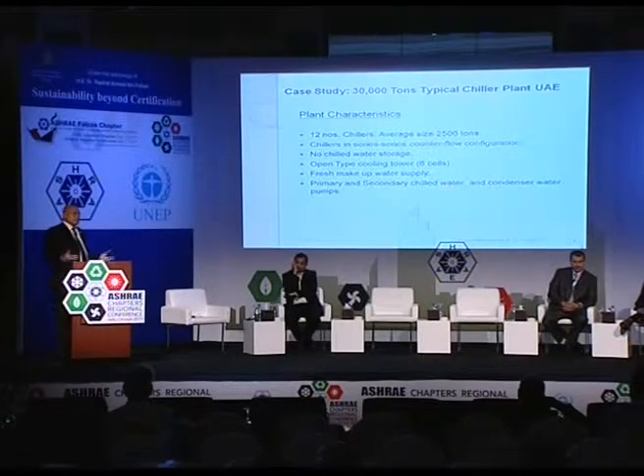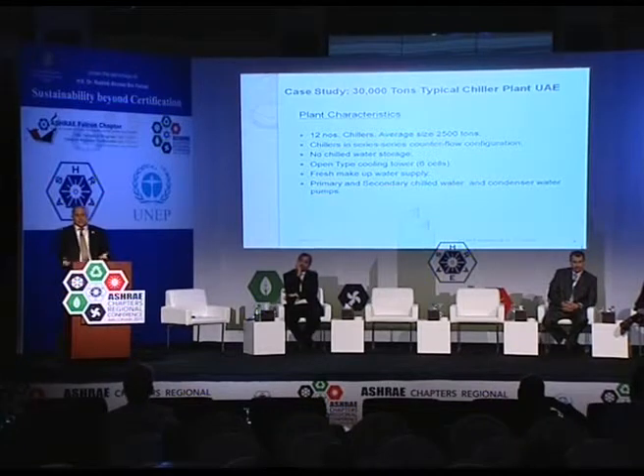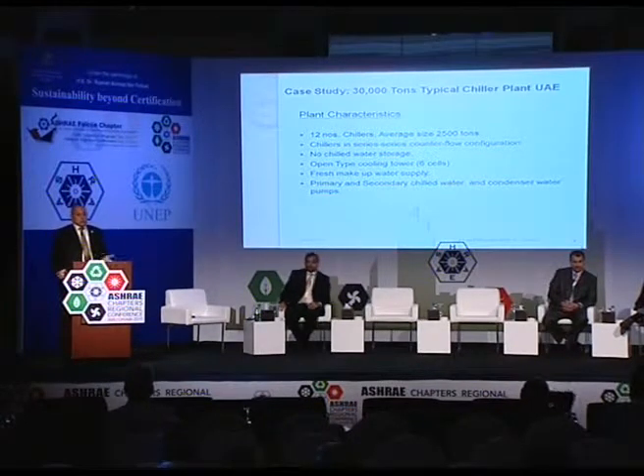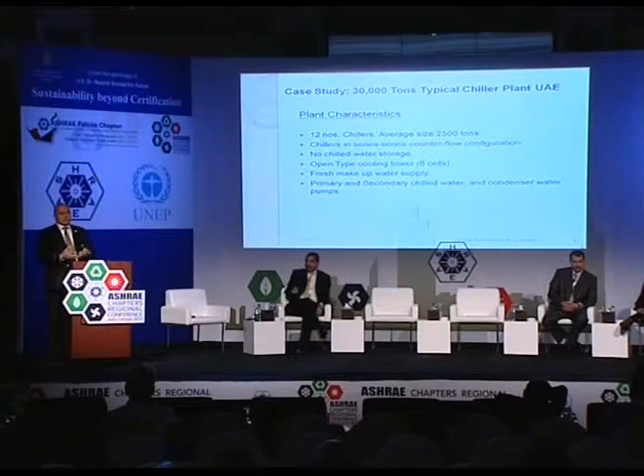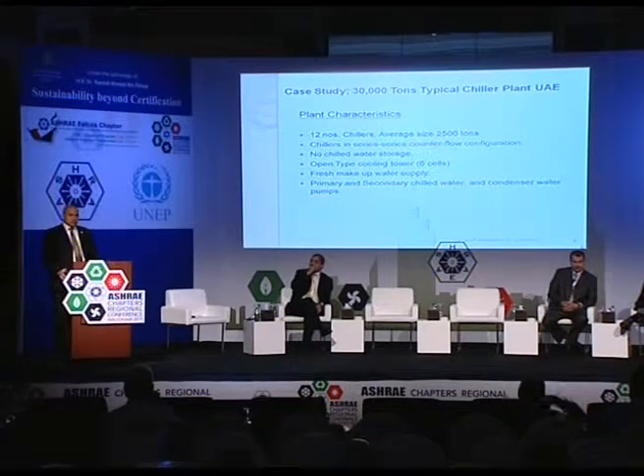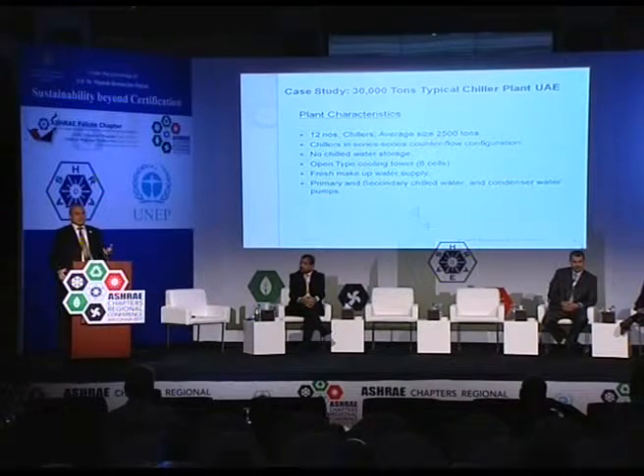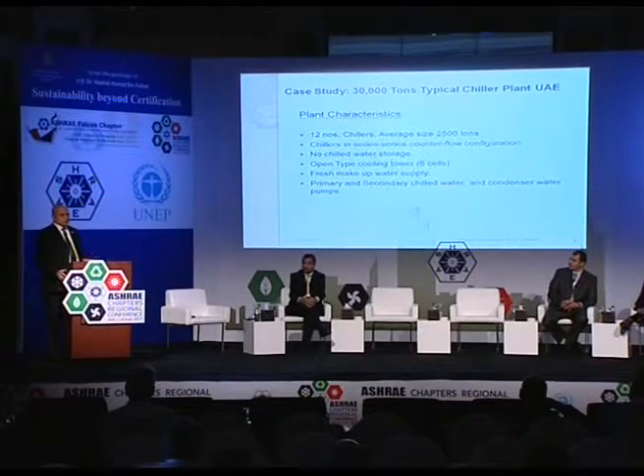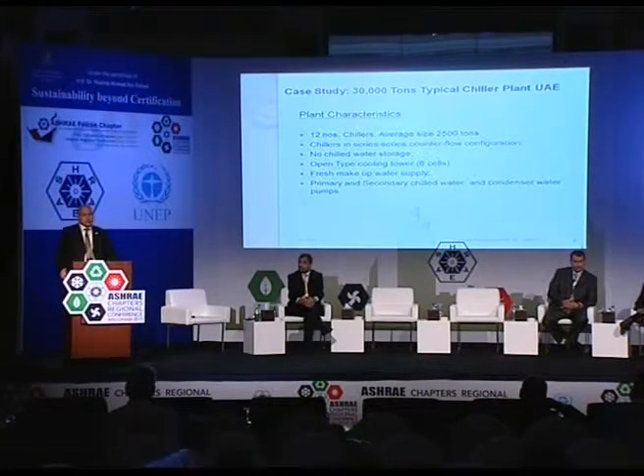The case study was done on a 30,000 ton typical chiller plant in the UAE. We used the most common configuration: 12 chillers in series counterflow, approximately 2,500 tons each, so each module is 5,000 tons. There was no chilled water storage, because at the time most plants built before did not have any water storage. It had open cell cooling towers, and primary and secondary chilled water and condenser water pumps.